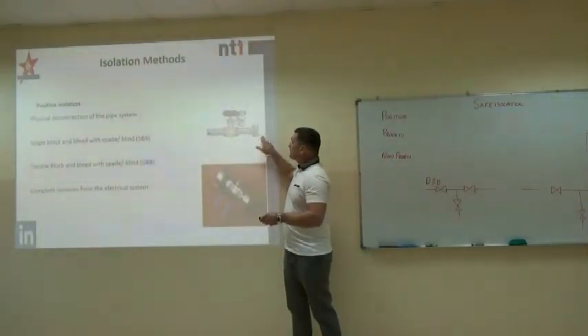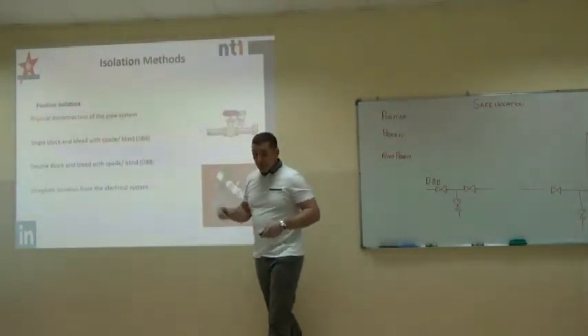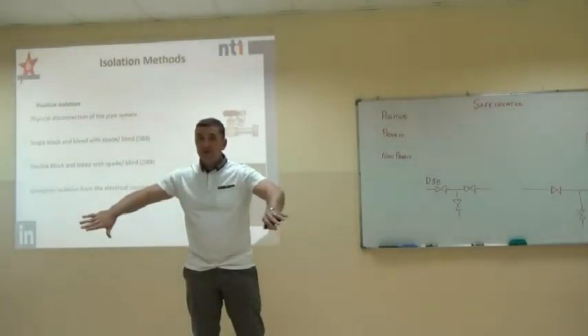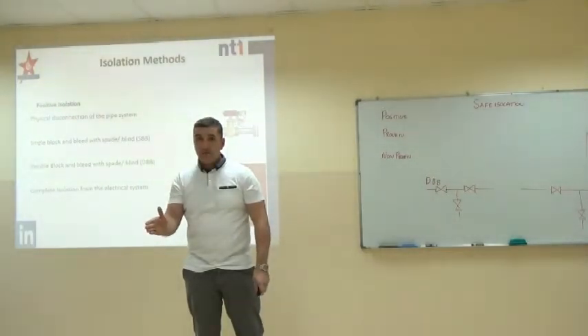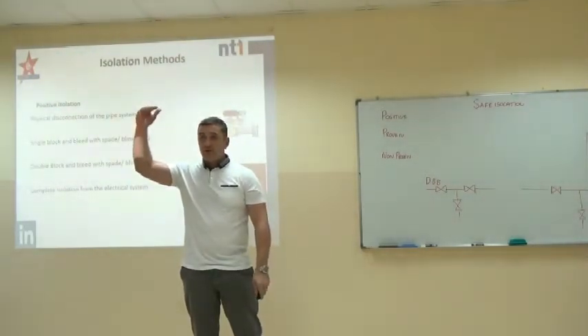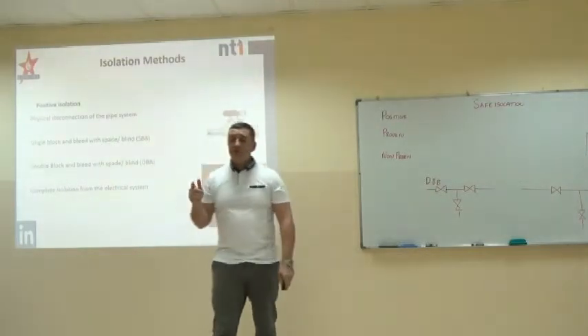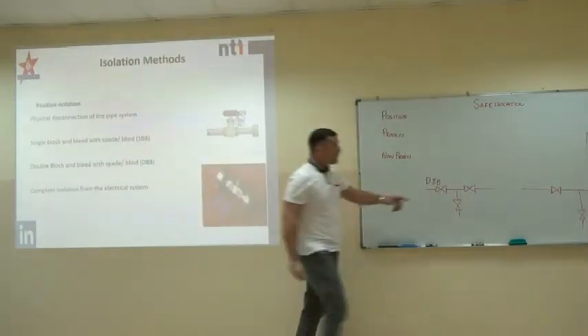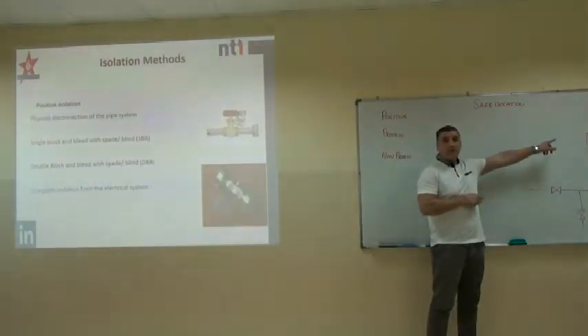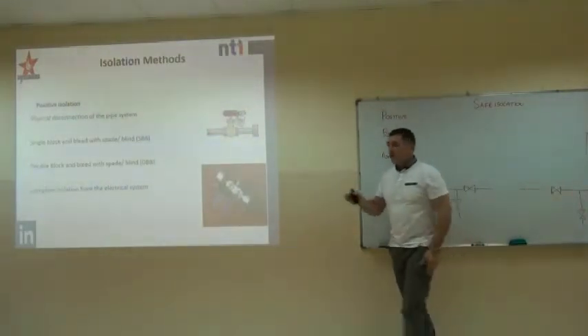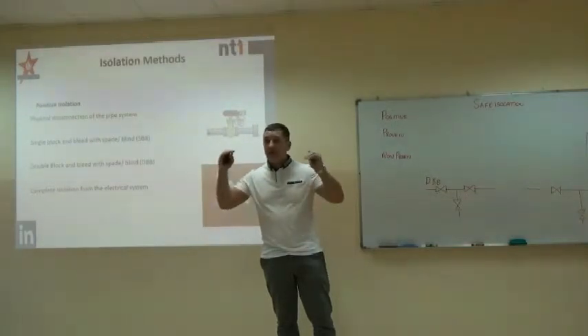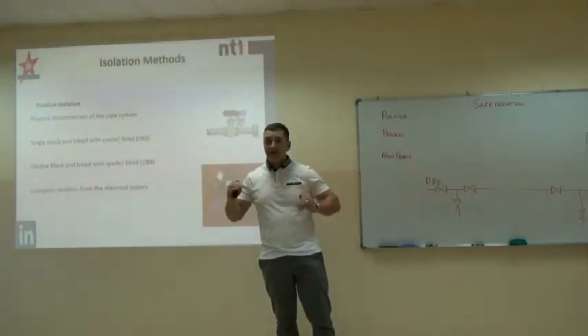Never leave anything open, and always back it up with full flange integrity procedures. The type of isolation we use depends on the hazardous energy. If we've got 30,000 litres of oil, then we want a positive isolation. If we've got 50 litres of water, then we might do a different isolation — it depends on the hazardous energy we're trying to isolate.